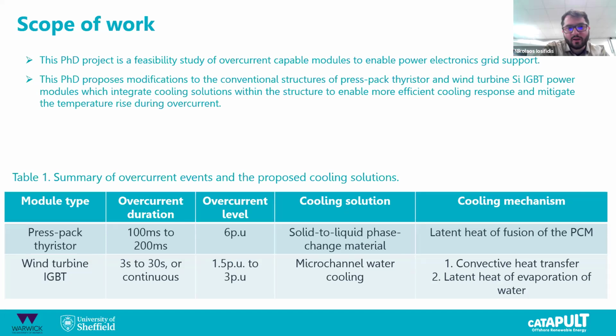So the scope of work is technically a feasibility study of overcurrent capable modules to enable grid support. We have simulated press-pack thyristors for very high current transients up to 200 milliseconds, and the cooling solution was phase change material cooling, which uses the latent heat of fusion of the phase change material when it changes from the solid to the liquid state. And for the wind turbine modules, we have tested already for transients up to 30 seconds for 1.5 per unit current, or continuous for slightly lower current. And the solution is microchannel water cooling, and the cooling mechanism is convective heat transfer, like in one regular heatsink, or sometimes the latent heat of evaporation of water when the heat flux is very high, when chips are required to inject a way higher current than they're supposed to. Next slide, please.